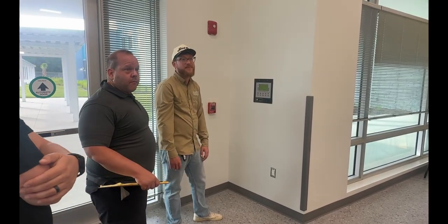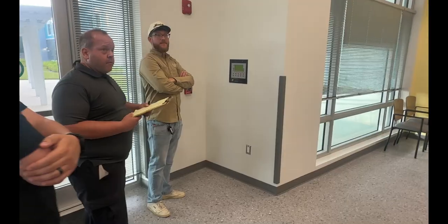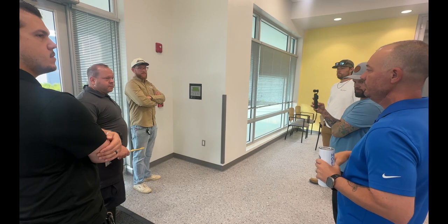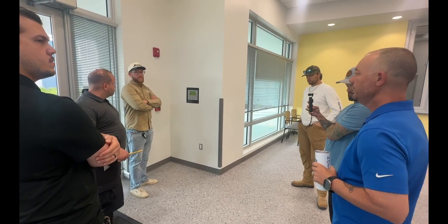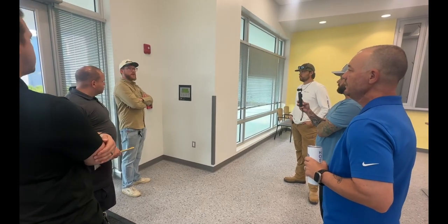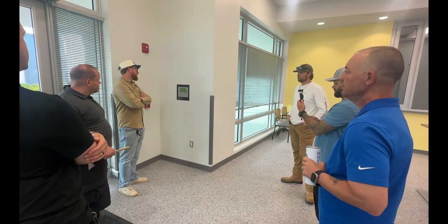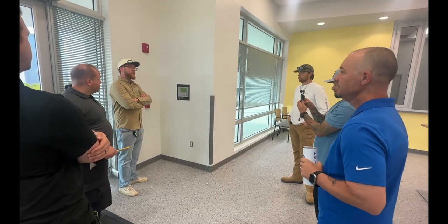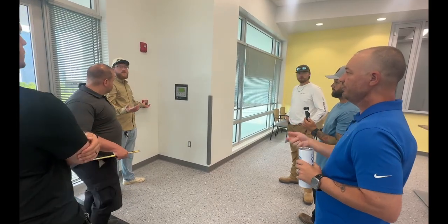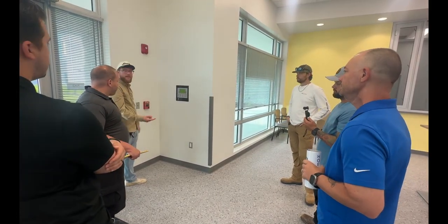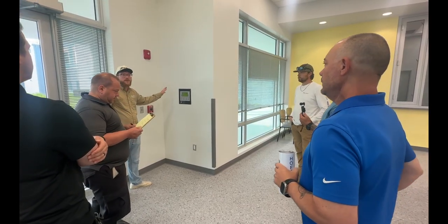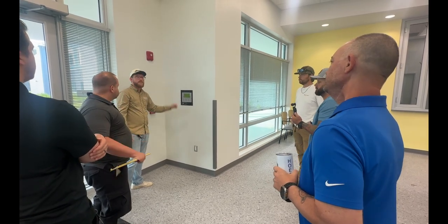So go back to the fire drills. Obviously we call it in, we say, hey, we're going to be on test. We do that same process, and then we can set it off with a pull station, or can we set it from here? You can, but I would prefer you just pull the pull station. It's easier if you just go ahead and pull the pull station. Now, all you have to do is there's a key. You open it up, flip the light switch back in, close it, lock it. Then you just go to the panel, everybody's in their designated location, everything's good to go. You just reset the panel.